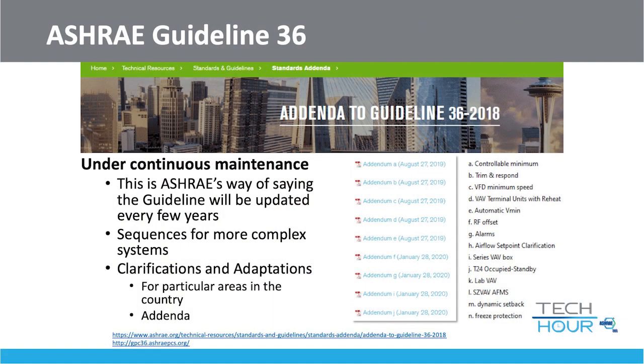So having demand-driven resets for everything from the air handling units or a chiller plant down to VAV terminals, and reducing reheat, are the main elements that make Guideline 36 more effective. There's also a lot of additional alarming and troubleshooting, such that when things go out of calibration, as they always will, there are alerts to the operators to make that visible.